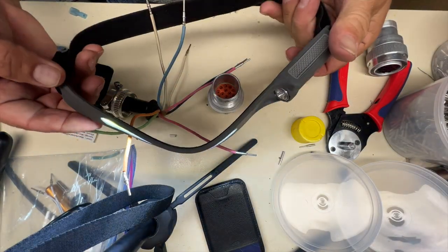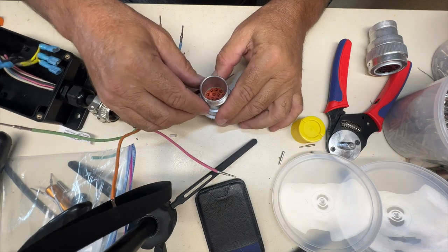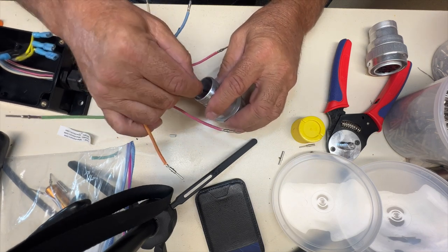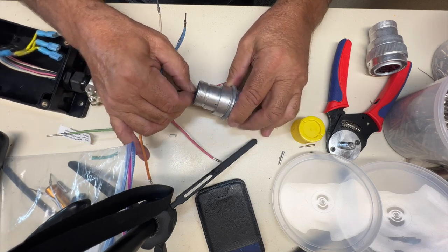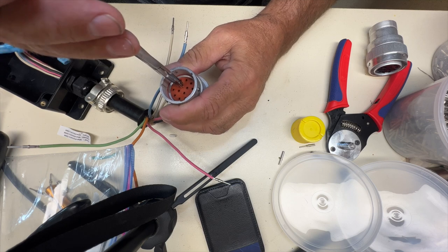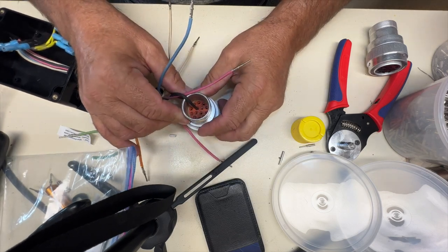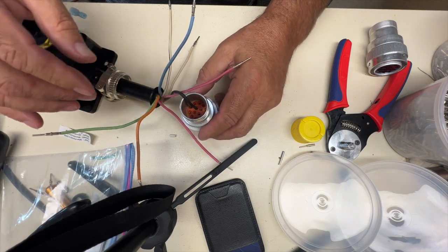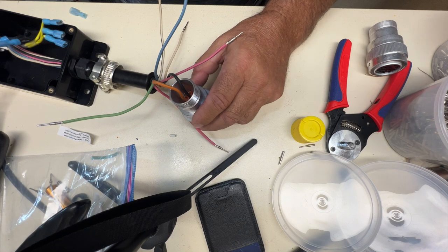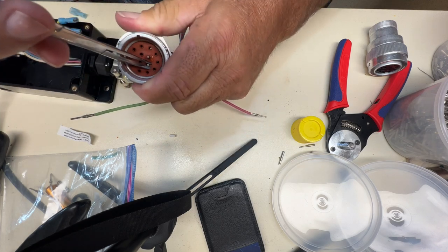I like to wear one of these headband lights when I'm working - it just gives me a little bit more light so I can see. Here we go. So we'll take our B. There are a few ways of installing this - I can just try to push them through; sometimes they'll slide right through and click. Sometimes they don't - you can use a little parachute forceps here, give a little pull just to make sure it's locked. You can push on it, make sure it goes through. So I did B. I'm going to do C - push that through. It doesn't want to quite go through; you can use the same forceps, kind of line it up and try to have a nice straight push. Push it down into place - there it goes, it clicked.